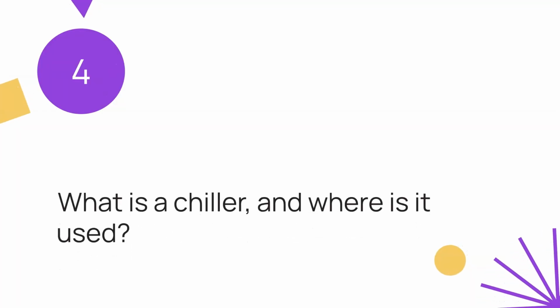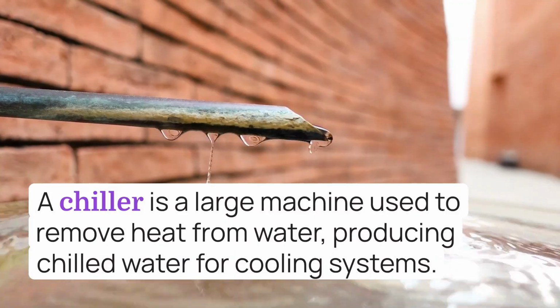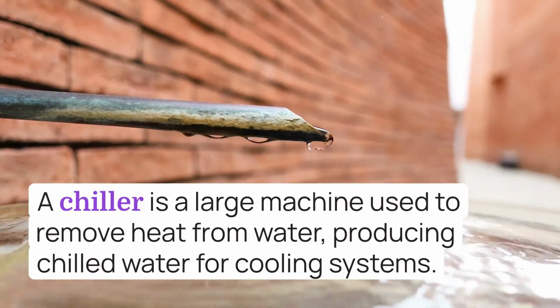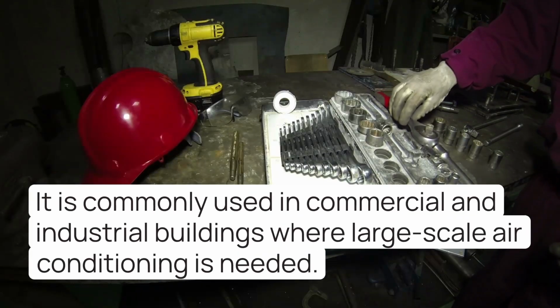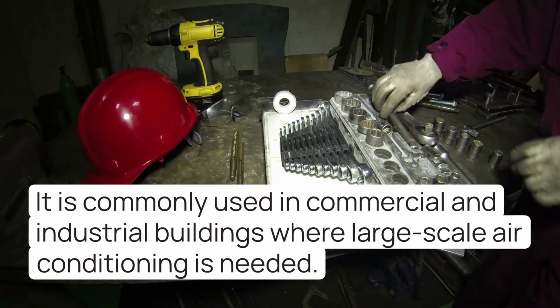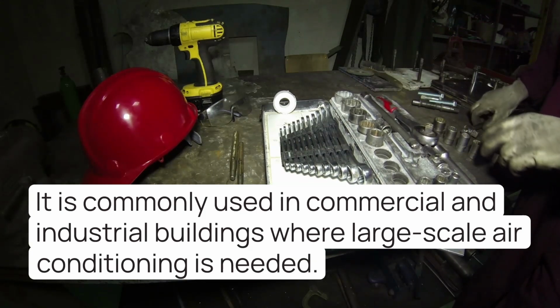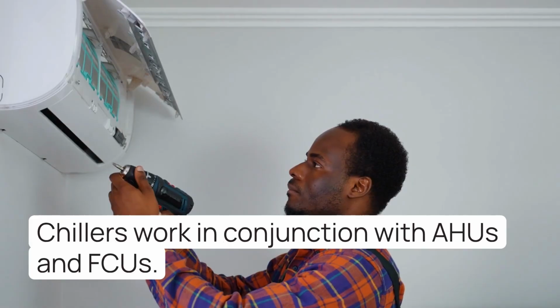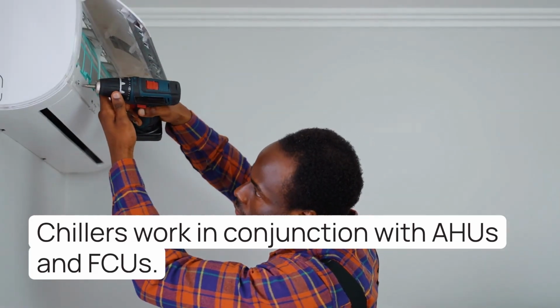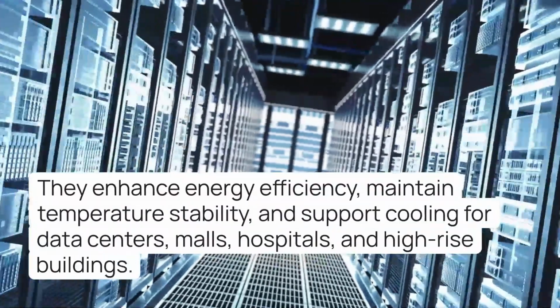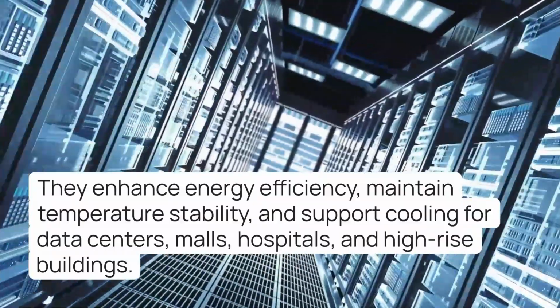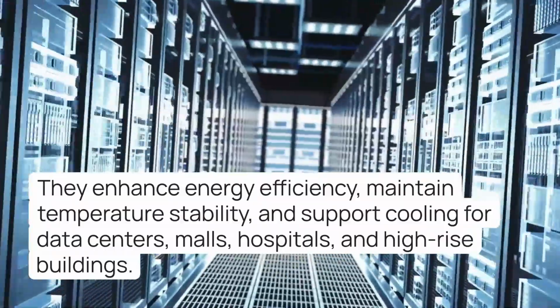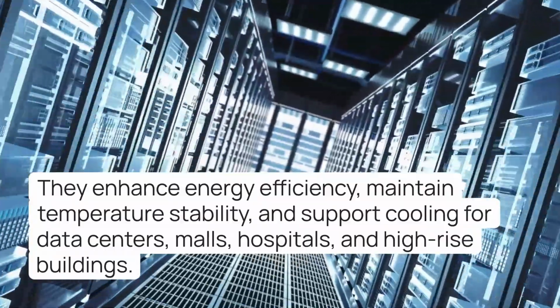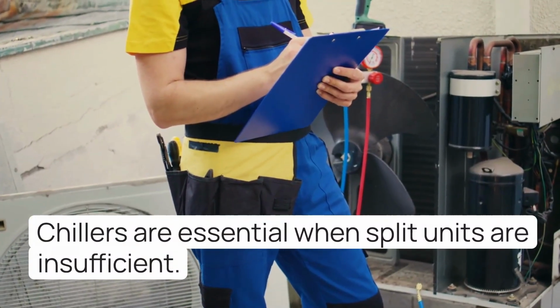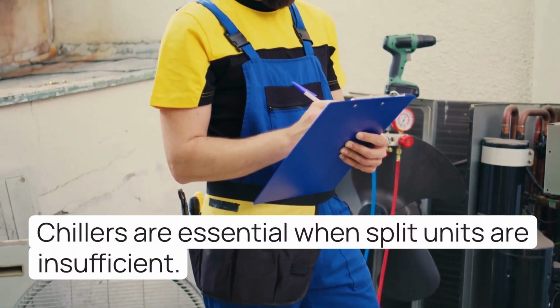4. What is a chiller and where is it used? A chiller is a large machine used to remove heat from water, producing chilled water for cooling systems. It is commonly used in commercial and industrial buildings where large-scale air conditioning is needed. Chillers work in conjunction with AHUs and FCUs. They enhance energy efficiency, maintain temperature stability, and support cooling for data centers, malls, hospitals, and high-rise buildings. Chillers are essential when split units are insufficient.